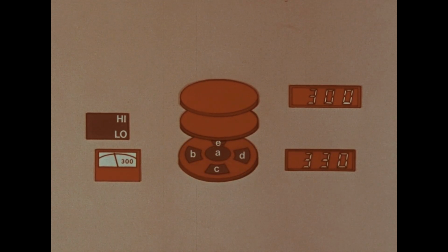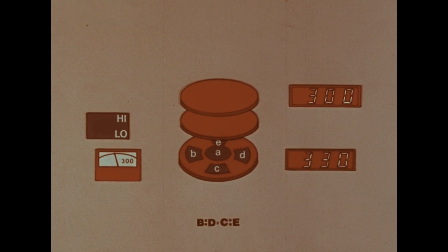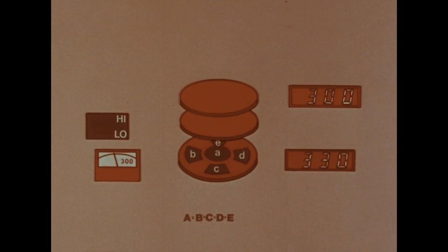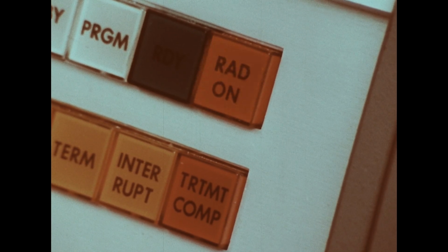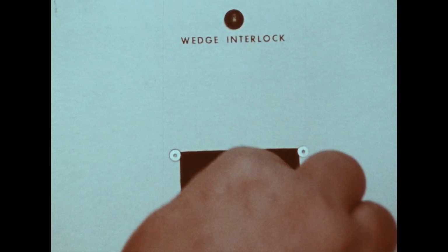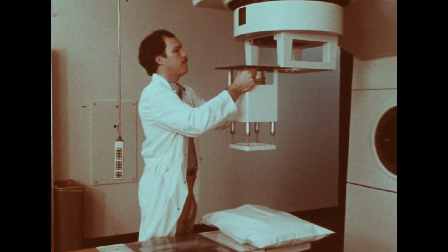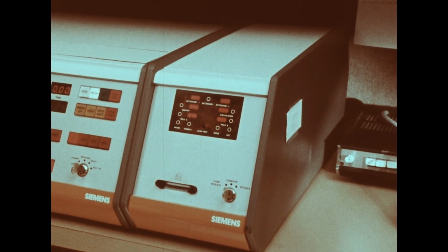There is another ionizing chamber assembly which is a multifunction safety system. It measures the secondary dose and discontinues radiation if the primary dose fails to do so. This chamber also monitors the dose rate, monitors the symmetry of the beam by comparing chambers B, D, and C, E, monitors field flatness by comparing A with B, C, D, E. If any parameter changes during treatment, the interlock circuit immediately terminates radiation and displays the cause. An accessory code interlock system, standard with all machines, ensures that the correct accessory is being used.